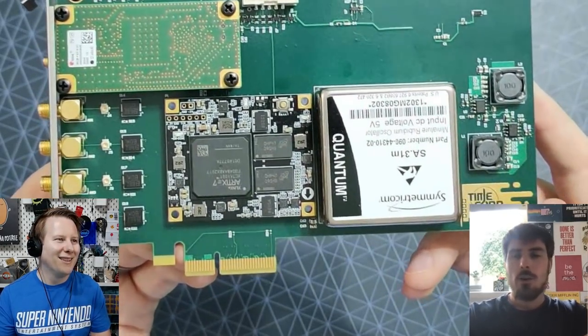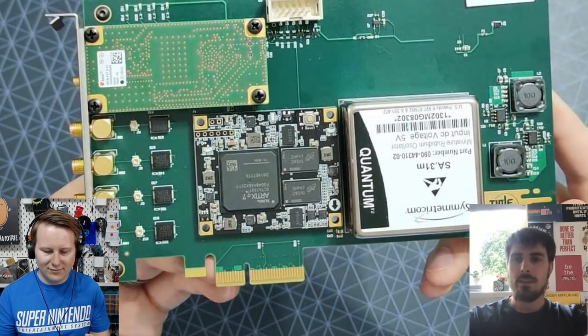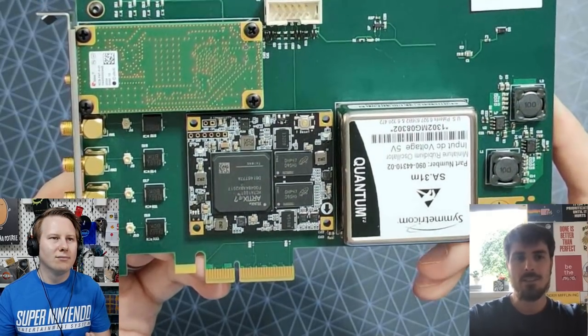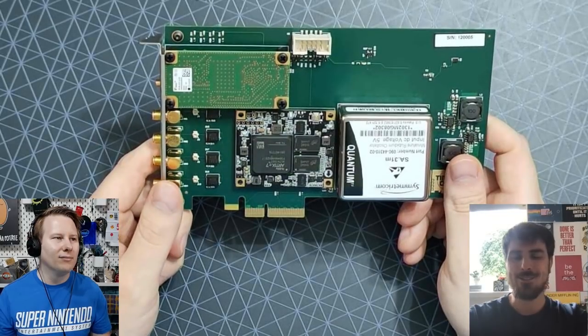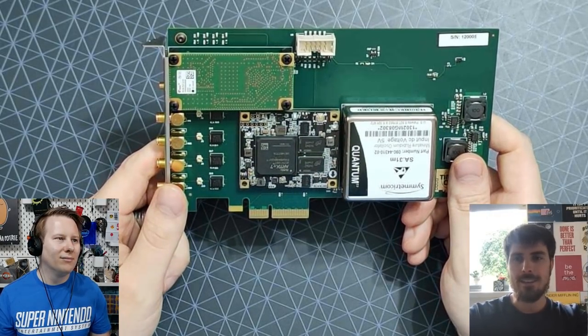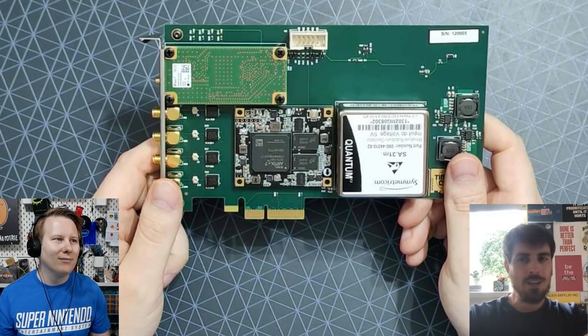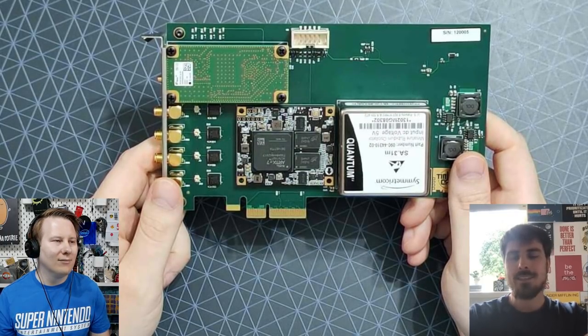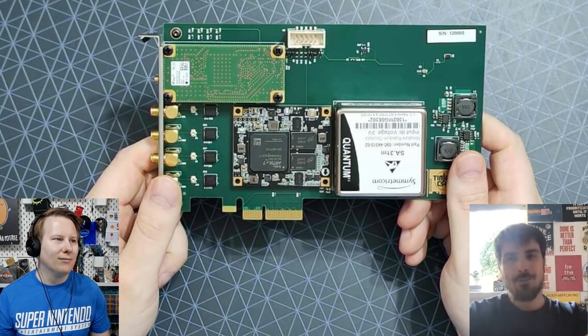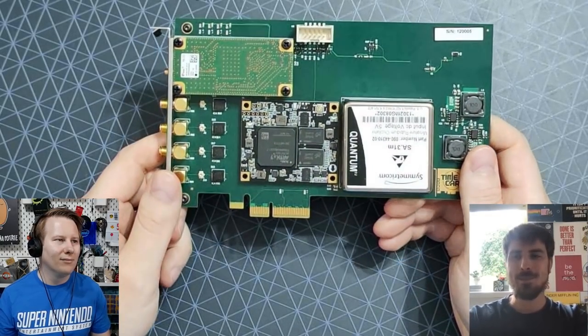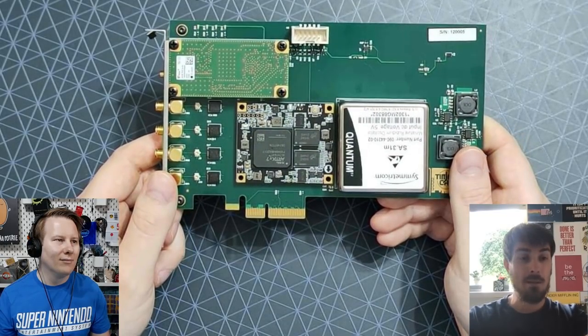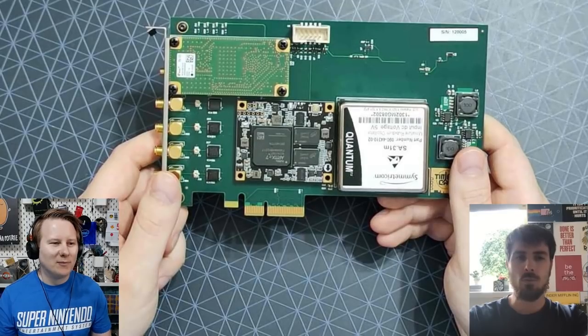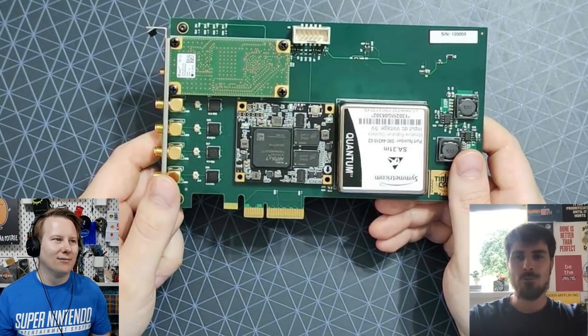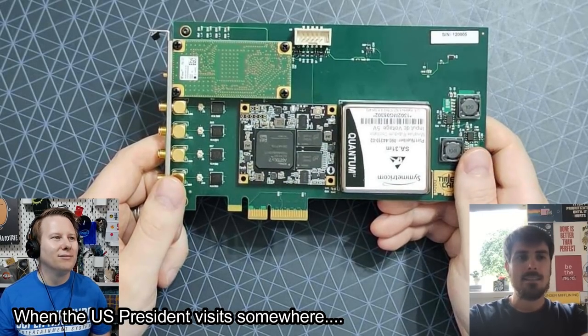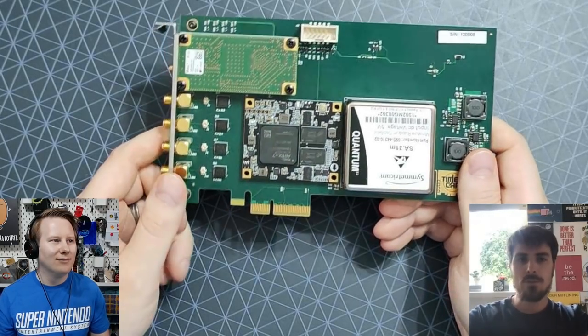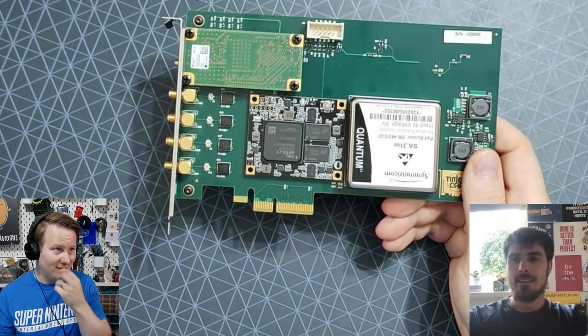So we receive the time with this receiver, but there are several problems which can happen just because of this wireless technology. First of all, you have to have a blue sky, a clear sky. If there is cloud or shadow or anything like that, like a plane passing by, you can have some sort of disruptions. But my favorite example is when some important people pass by, they often jam GPS. This is actually a well-known situation when GPS stops working in a radius of 40 kilometers around some event. By mistake or on purpose, you may have your GPS jammed, and then it may lead to outages.